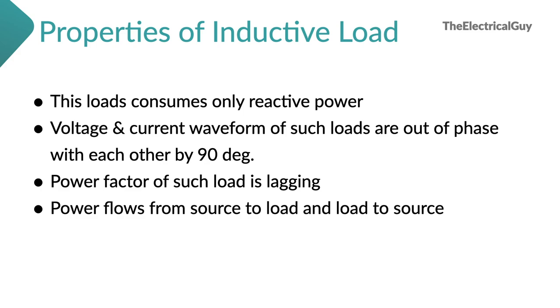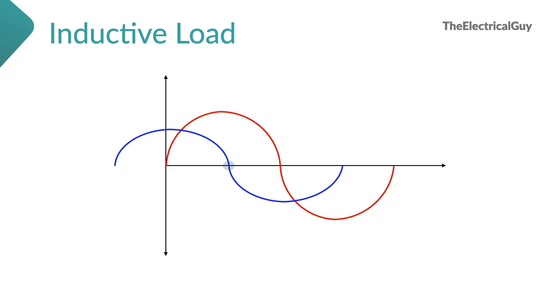This type of load is not as easy to handle as resistive loads — they create a lot of problems in the system, but of course they are equally important. Since current lags behind the voltage by 90 degrees in such loads, switching becomes difficult. As we know, a circuit breaker opens at the current zero condition — in inductive loads, when current is zero, voltage is at its maximum. And hence when the circuit breaker opens, the voltage across the breaker contacts is maximum, making switching a critical operation. Such loads also heavily affect the power factor of the system, and hence the electricity bill goes up.